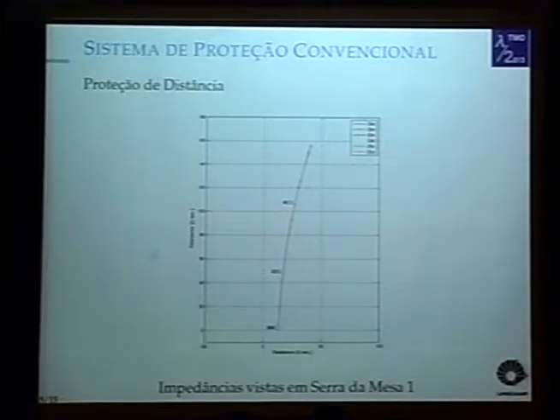We have put here 20 ohms of fault. That's why it's not at the origin of the fault impedance. For faults, this is the impedance seen in Serra da Mesa 1 for faults happening in this segment. So here we have a conventional behavior that is expected by everyone using line protection. We almost have a line here, so we can use the distance protection, for example, for protecting the corresponding segments of the line.